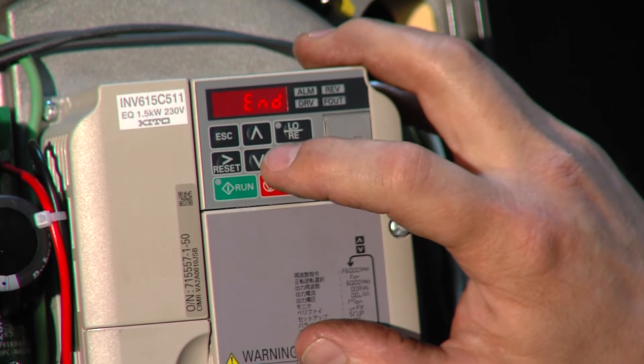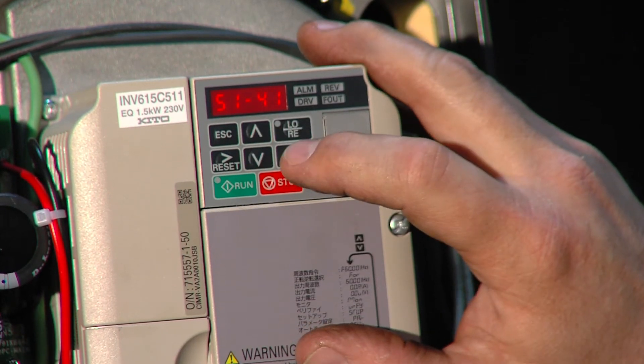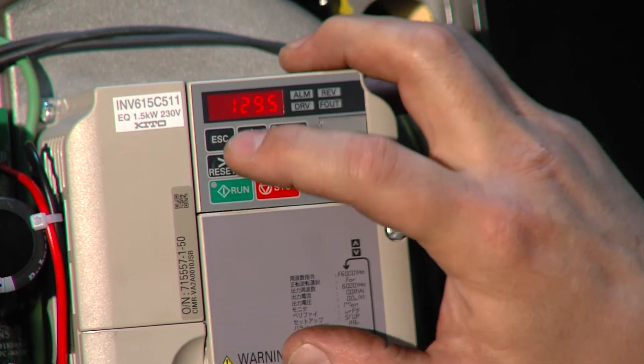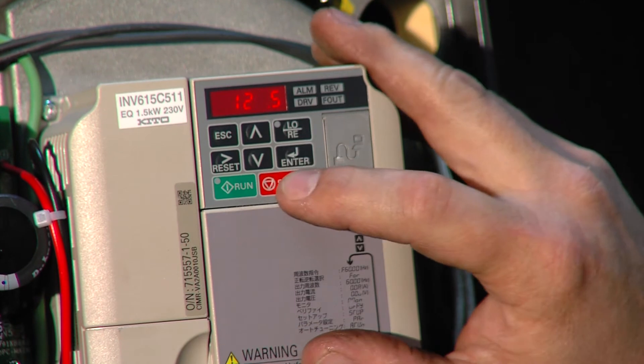Press enter, use the up arrow to go to S1-41. That's the second parameter we have to adjust. Right now that's 129.5; we're going to change that to 127.5. Press enter, escape, escape.